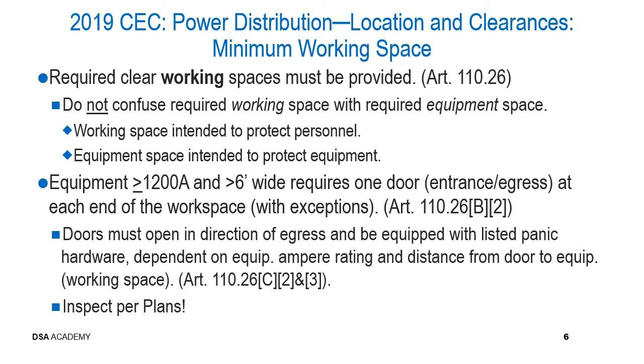Now, with respect to, again, high-powered equipment exceeding 1200 amps, the egress and entrance doors to the area, again, must open in the direction of egress. They also must be equipped with listed panic hardware, and dependent on the equipment ampere rating and the distance from the door to the equipment, the working space itself may vary. And again, this is going to be determined, verified, and documented on the approved plans by the design professional. So again, I can't stress this enough that it is so important that project inspectors inspect per the plans, primarily for electrical construction.